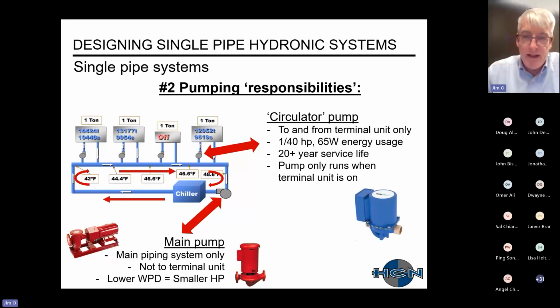And then secondly, at the terminal units, you have a circulating pump. These are typically very, very small. They have a long service life, and this pump only runs when the terminal unit is on. All right, so once again, you have a similar VFD system on your main pumping system as your zones and units come on and off.